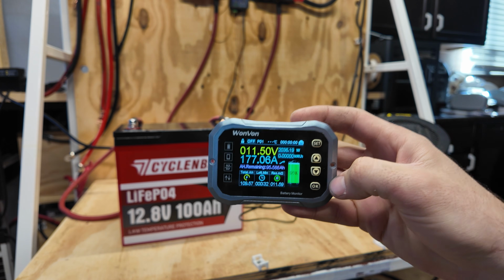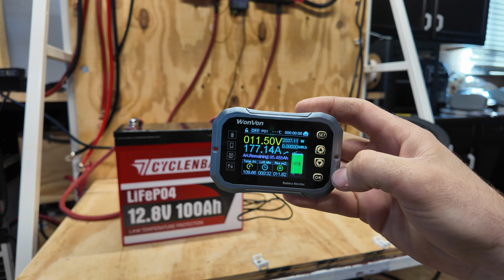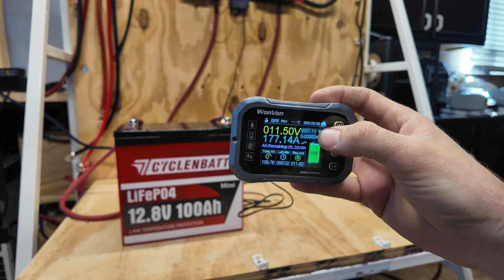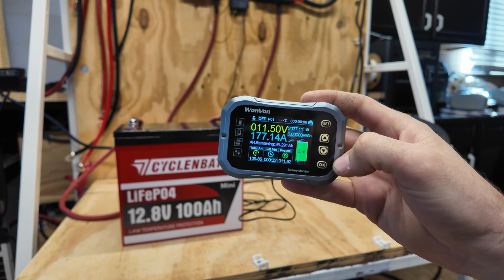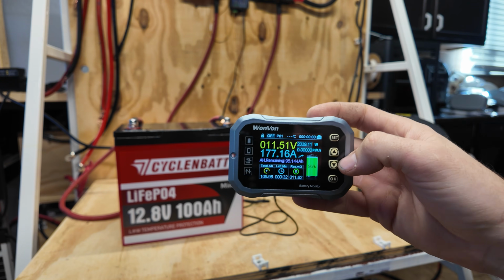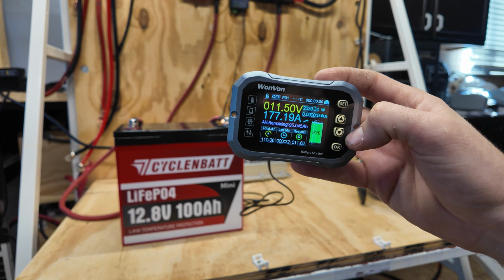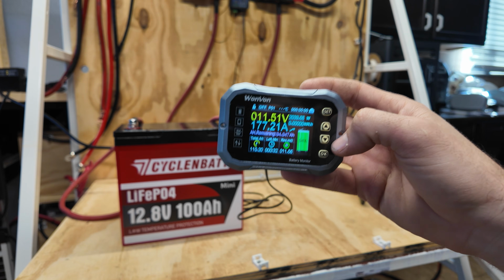I'm not gonna be able to get it any higher than this, because when it goes over 230 amps, the voltage dips too much for my inverter and it actually shuts off. So we're gonna call the test here, let it run at this load level, and see if the battery will shut off or not.